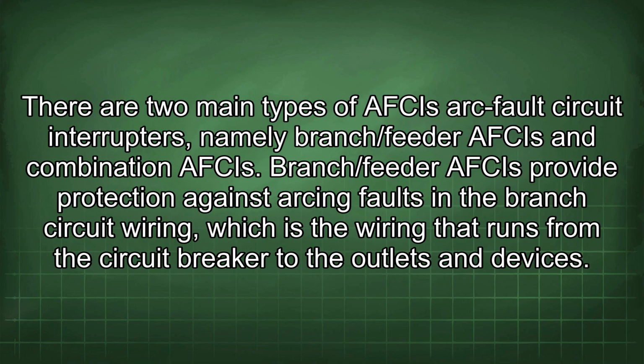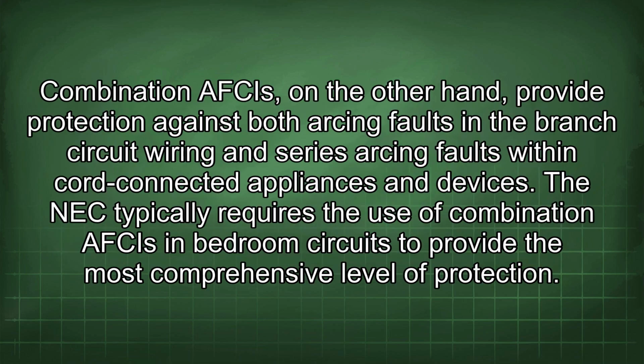There are two main types of arc fault circuit interrupters, namely branch/feeder AFCIs and combination AFCIs. Branch/feeder AFCIs provide protection against arcing faults in the branch circuit wiring, which is the wiring that runs from the circuit breaker to the outlets and devices. Combination AFCIs, on the other hand, provide protection against both arcing faults in the branch circuit wiring and series arcing faults within cord-connected appliances and devices. The NEC typically requires the use of combination AFCIs in bedroom circuits to provide the most comprehensive level of protection.